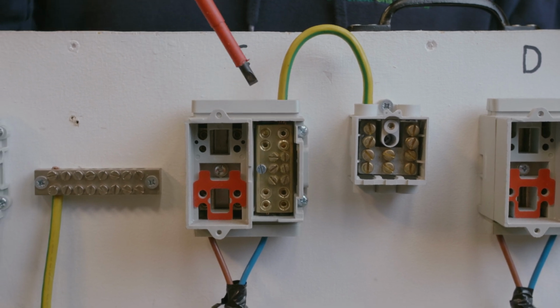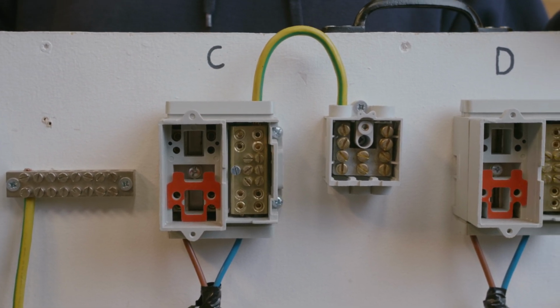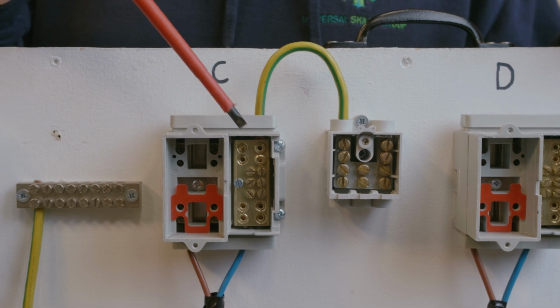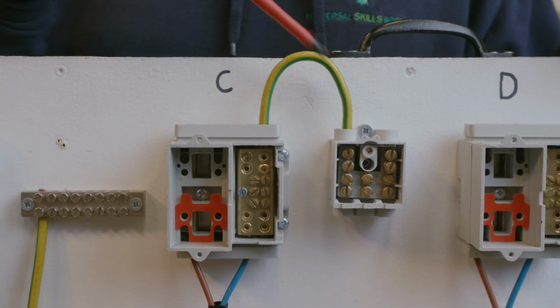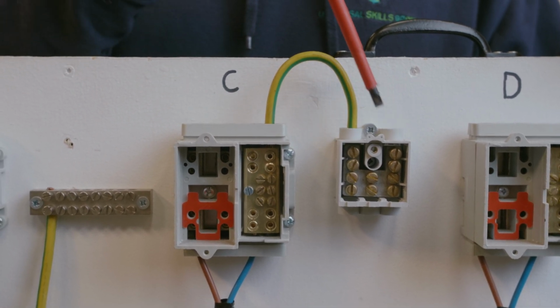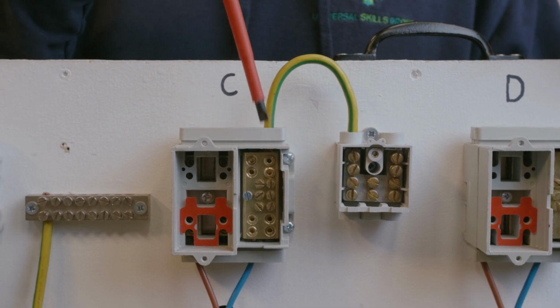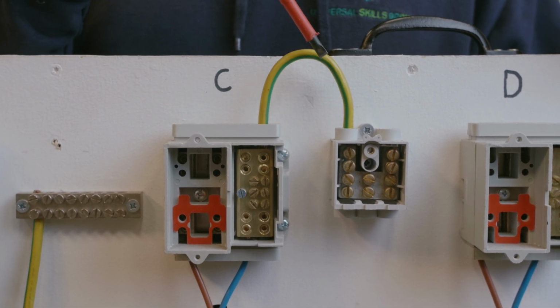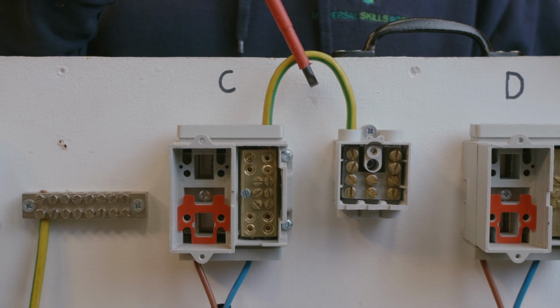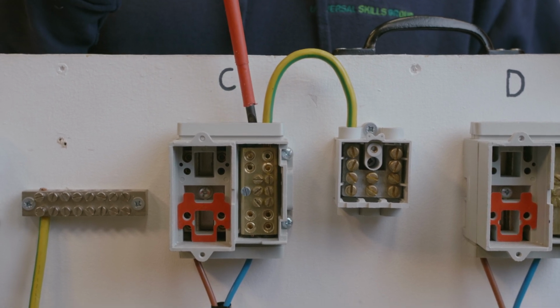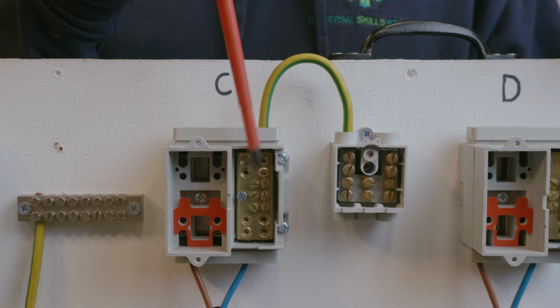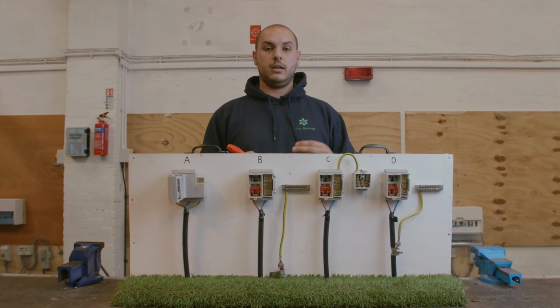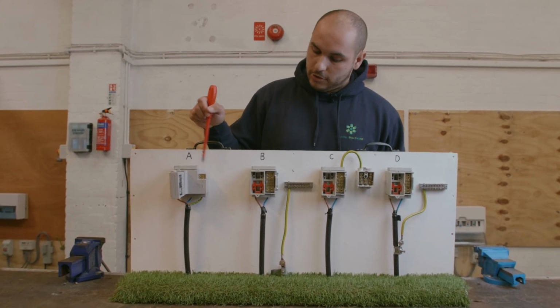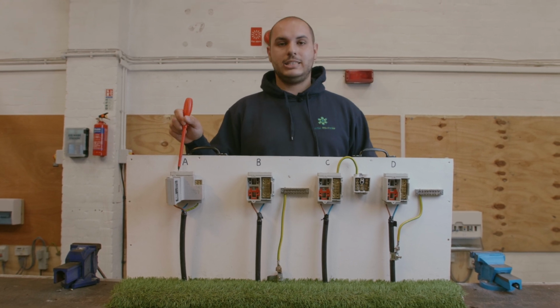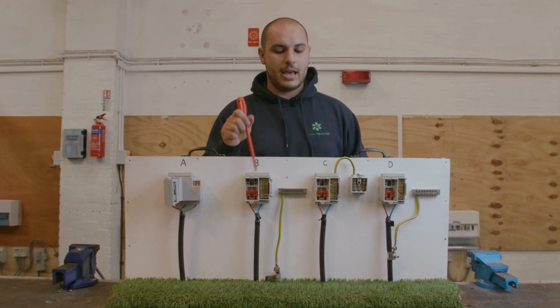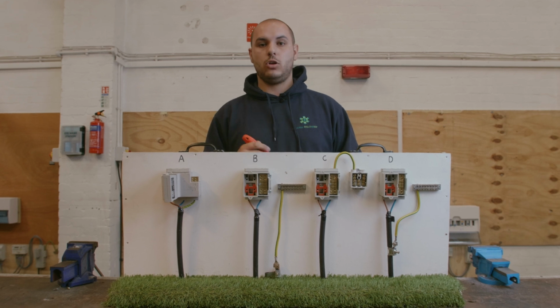Okay, so that is classed as a TNCS or PME setup, and that is where the neutral and earth are combined. So the main earth can either go into that block there, which is ultimately linked across and goes into your neutral, or you could just use your main earth from your consumer unit, which would just go straight directly into the cutout, into the neutral point itself. Okay, so now we've looked at the earthing arrangement we've got in front. So we've got a TNS, we've got a TT, and we've got a TNCS or PME.